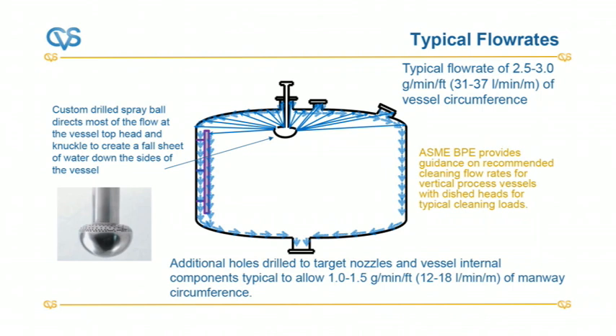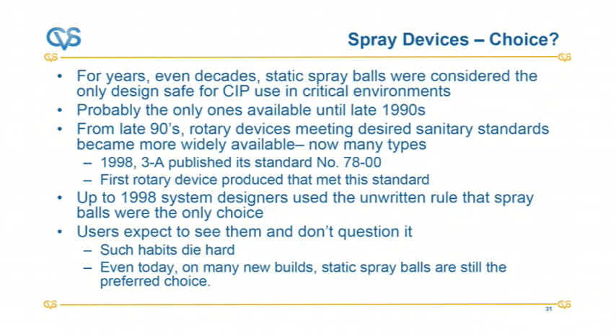But if we're using a static spray device, then usually we'll have custom drilled holes, and we need to test that with riboflavin. We may then have to go back and drill more holes or change the spray device to make sure we get full coverage. But that will give you a reasonable level of clean, though maybe not the most effective clean.